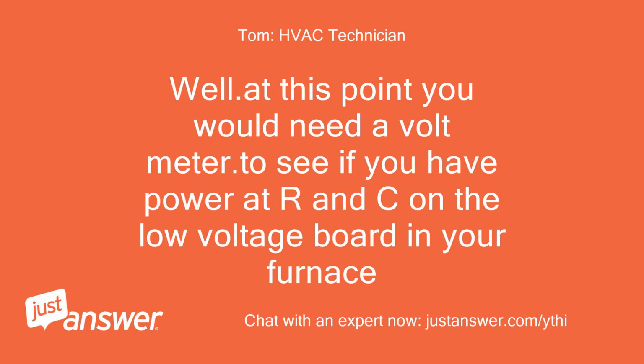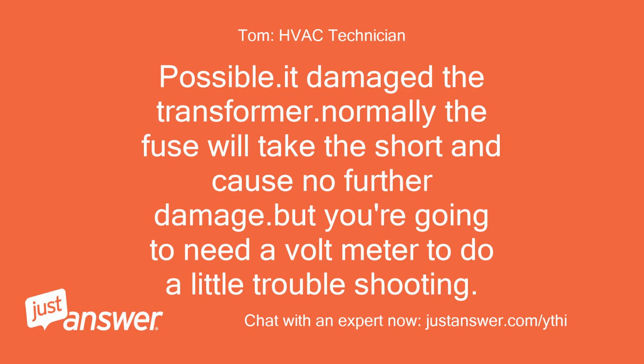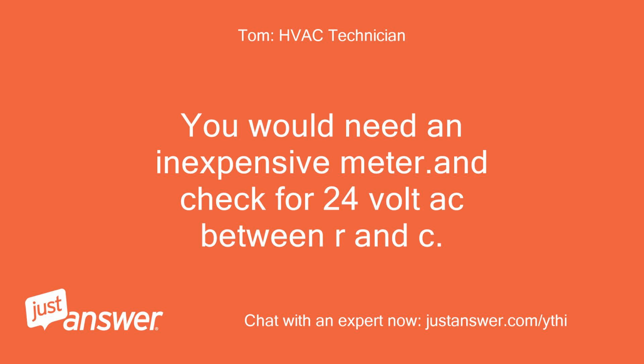Well, at this point you would need a voltmeter to see if you have power at R and C on the low voltage board in your furnace. Possibly it damaged the transformer. Normally the fuse will take the short and cause no further damage. But you're going to need a voltmeter to do a little troubleshooting. You would need an inexpensive meter and check for 24 volt AC between R and C.